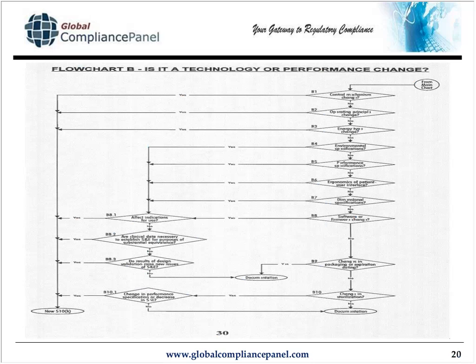Okay. If you look at B10, the question is, change to sterilization, yes or no? In this case, the questioner says, yes, we are absolutely changing from steam to gamma. So the question then is there a change in performance specifications? What that means is when your device, the performance of your device under steam, the previous sterilization, how does that performance compare to the performance of your device after exposure to gamma sterilization? Not just performance, but also physical characteristics.